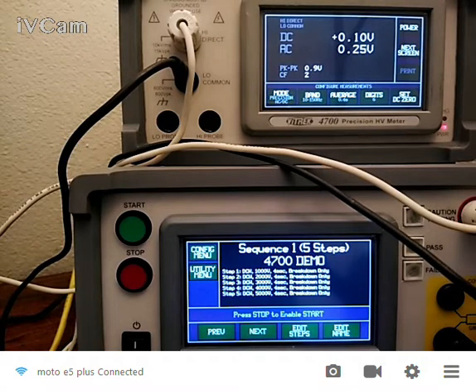Hello, this is Glenn Broderick, and I'm going to do a quick demo of the 4700 high voltage meter. So the 4700 is good for calibrating any kind of high voltage equipment, but quite often it's used for calibrating hipots. So what you see here is I have it set up, there's a hipot on the bottom, a V7X hipot from Vitrek, and the 4700 that we're looking at today is on top.